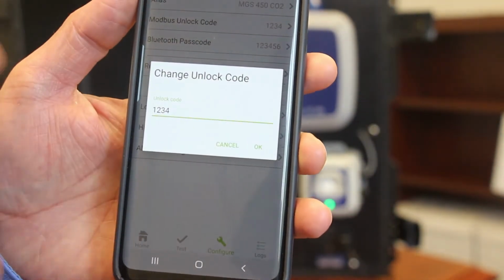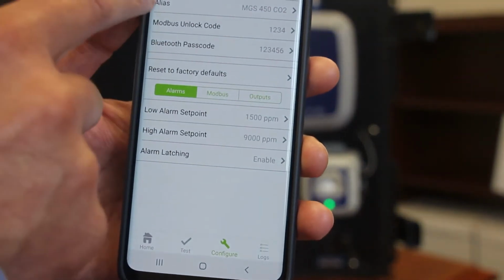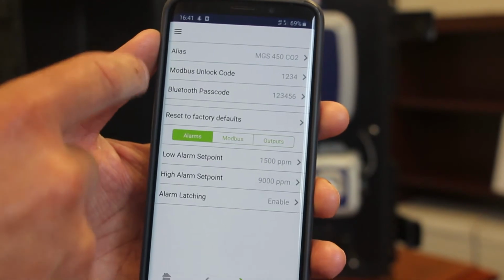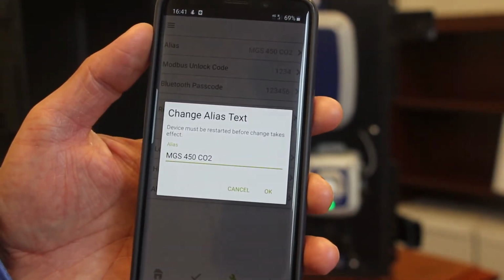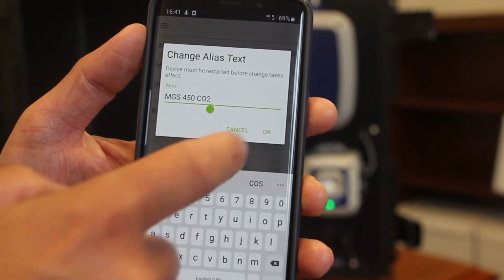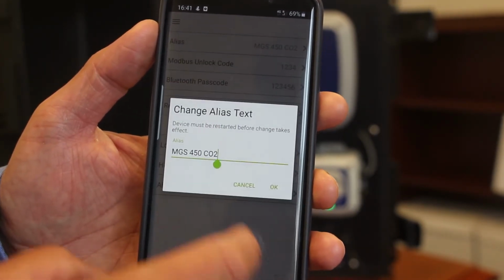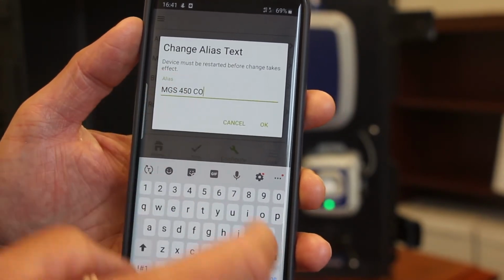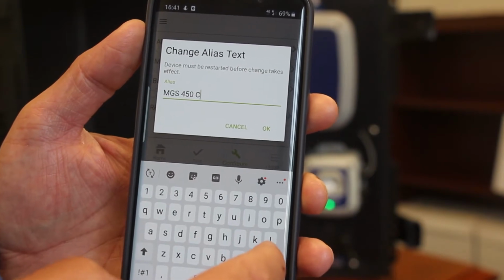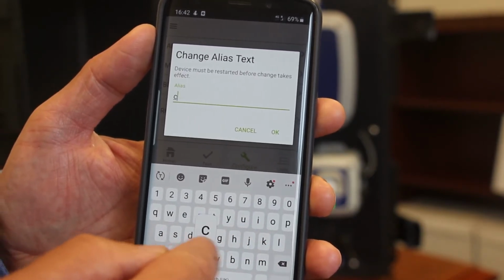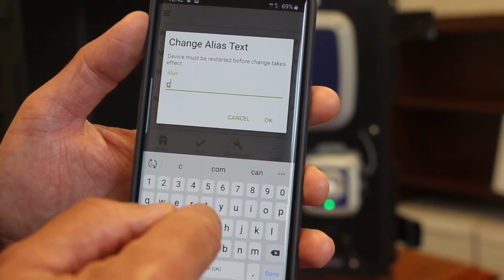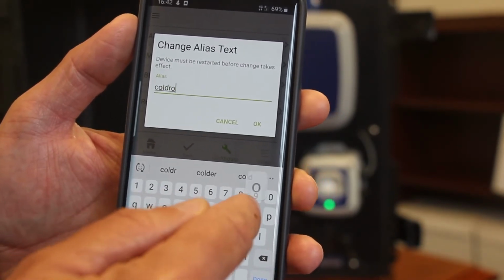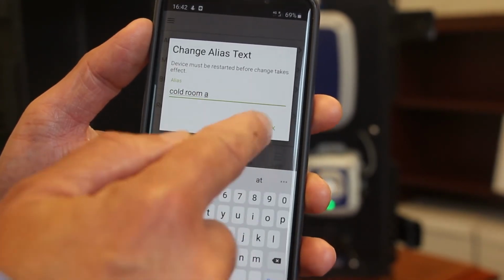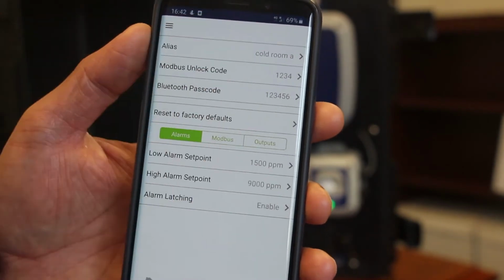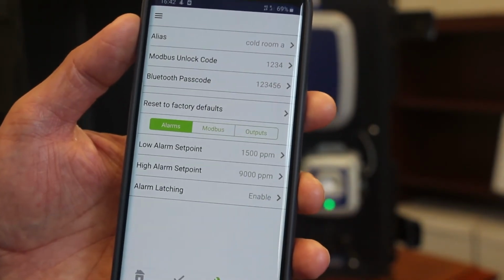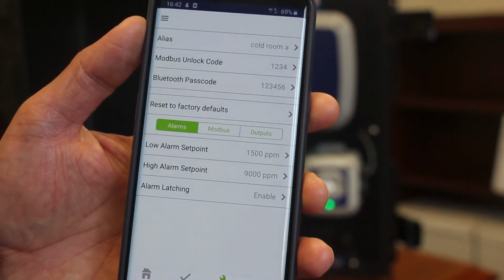So if I just go through each of the different options here, so you'll see the different variations across the screen here. So we have the alias button. So this is where you can go in and you can input a different name for the location of the detector. So as you can see, the default is the MGS 450 CO2. You can go in here and you can change this to say cold room A, for example, and you can click OK, and the alias automatically changes to cold room A here. So you can do that across your facility to have a relevant alias for your detectors.